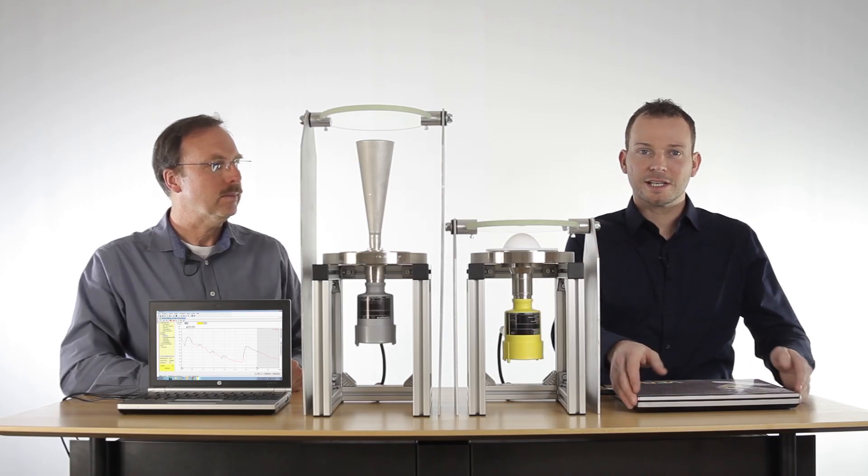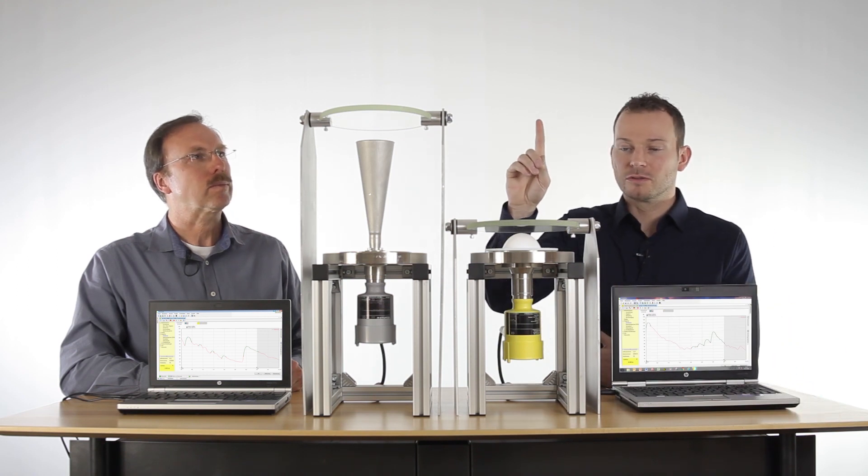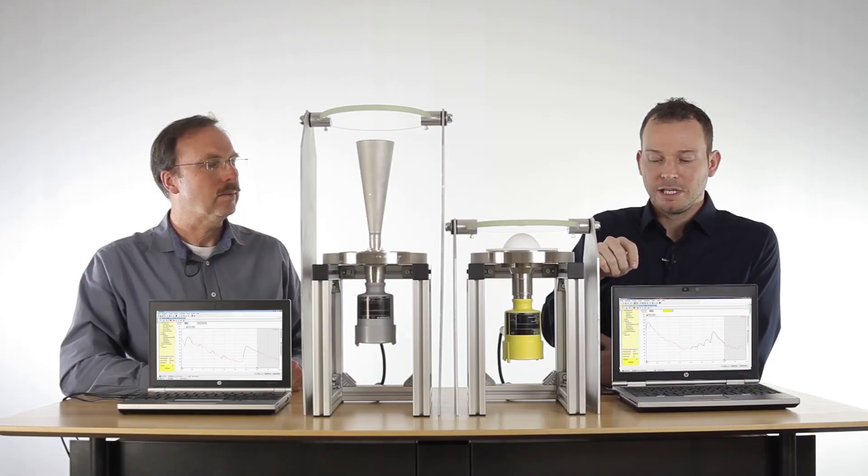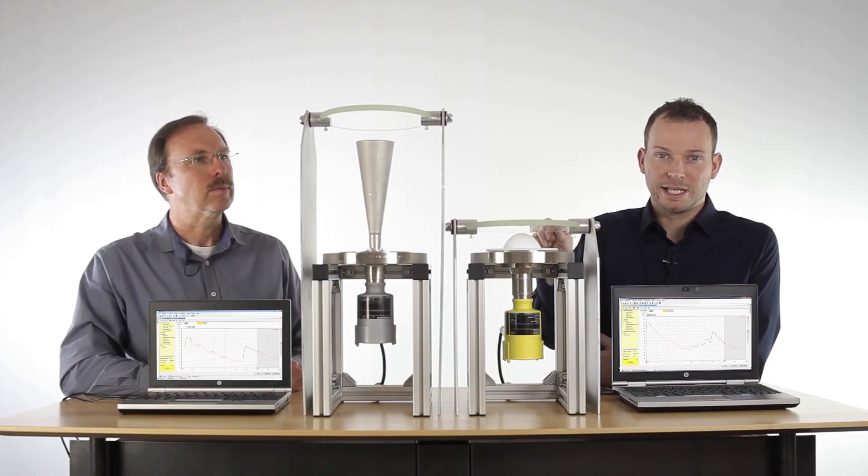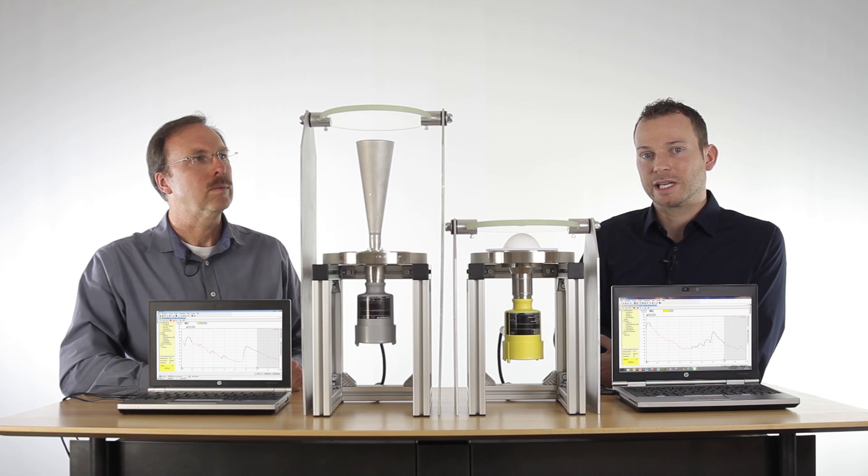On this side we have the Vega Pulse 64. We've mounted it the same way, measuring up to the roof through this glass. If you look at the echo curve, you see the reflection from the glass, but there are no multiple reflections, so there are no false signals in the near range - you have only the product echo in the back.